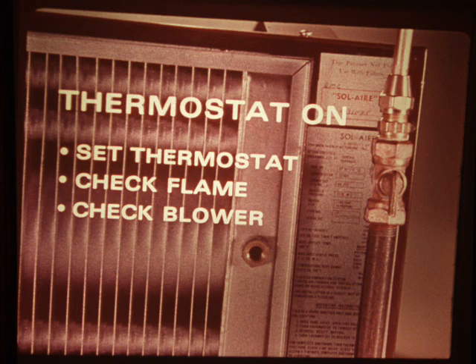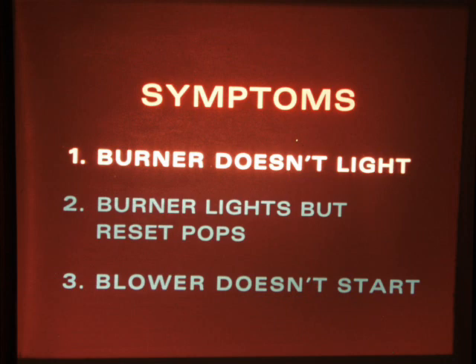To begin to troubleshoot the furnace, first set the thermostat to call for heat. Watch for a flame in the sight glass and listen for the blower to start up. You will determine what the actual malfunction is by what you observe. The burner does or does not light, the blower does or does not start. The first furnace problem we'll cover is the situation when you observe that the burner won't light, but the blower does start up.